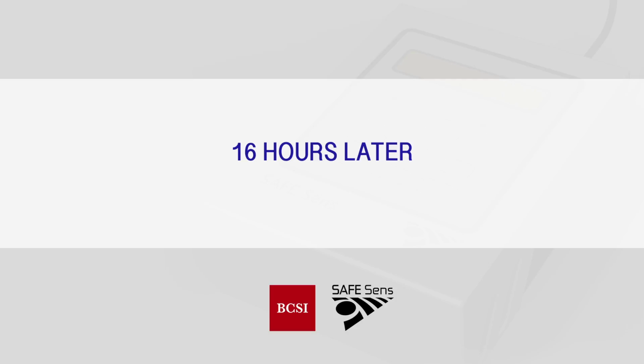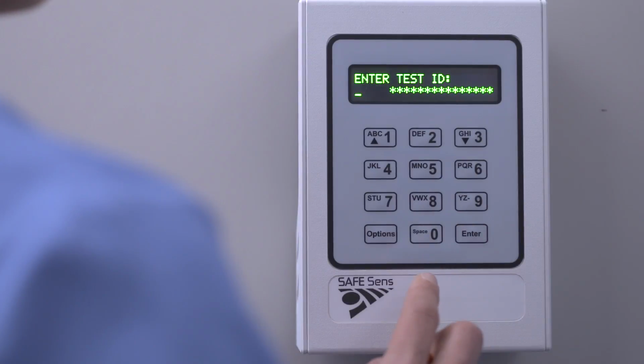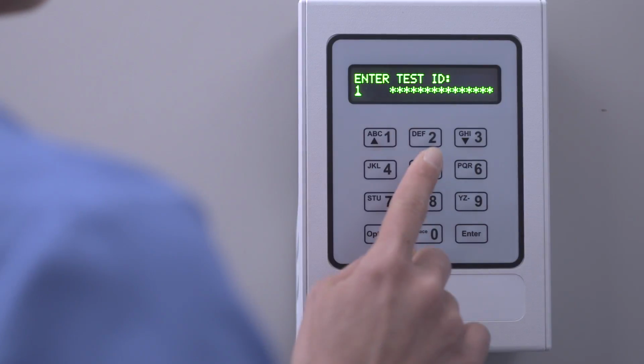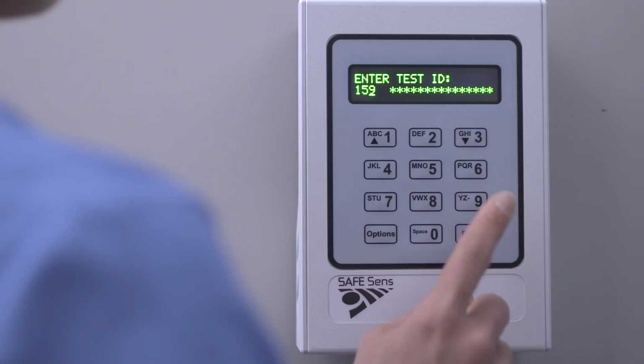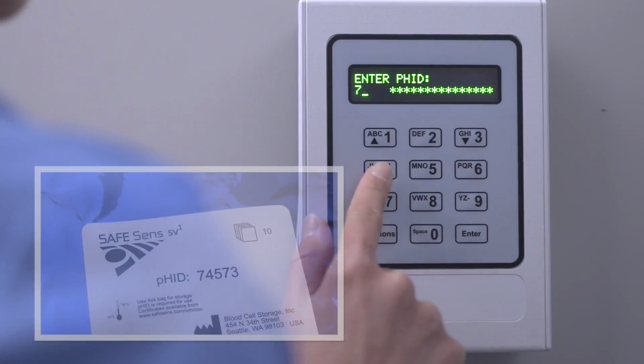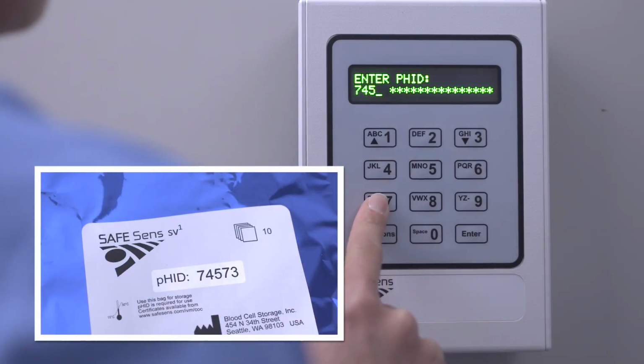At this point, the sensors have been in the incubator for 16 hours. Now we will start a test on the SAFE Sens. Press Enter from the home menu screen and enter a test ID. 159 will work, and press Enter. Then type in the pH ID. This is found on the blue packaging label of the sensors. Press Enter.